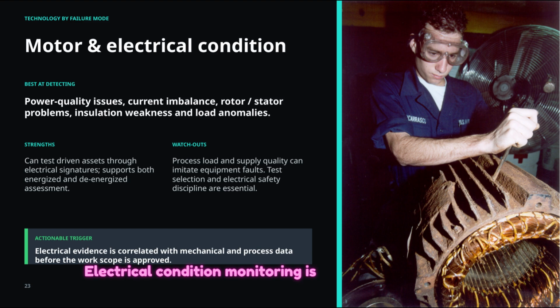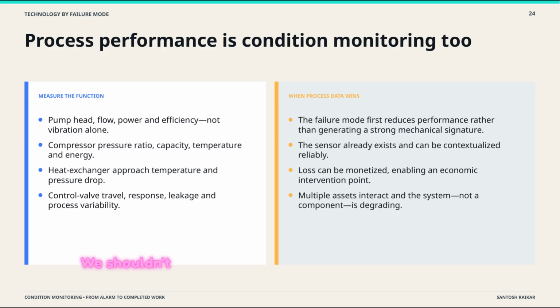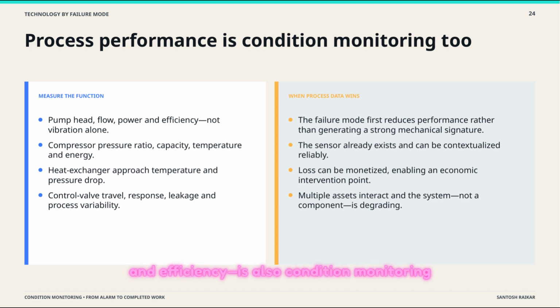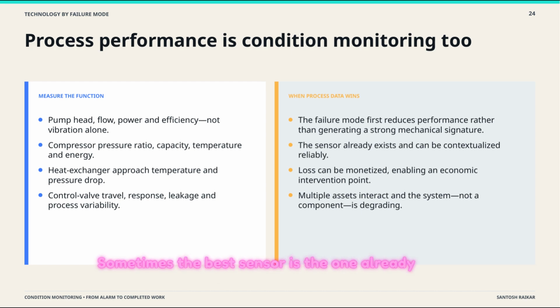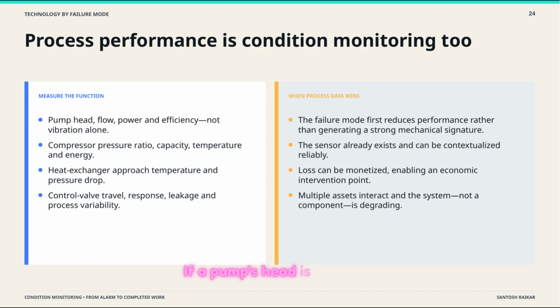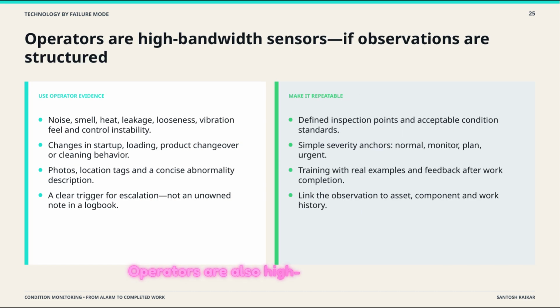Electrical condition monitoring is growing in importance. It allows us to detect rotor and stator problems and even issues in the driven asset by looking at the power quality and current signatures. Because process loads can imitate electrical faults, we always correlate this data with mechanical evidence before approving a work scope. We shouldn't forget that process performance data, like flow, pressure, and efficiency, is also condition monitoring. Sometimes the best sensor is the one already in the SCADA system. If a pump's head is dropping, that might be a better indicator of internal wear than any vibration probe will ever provide.